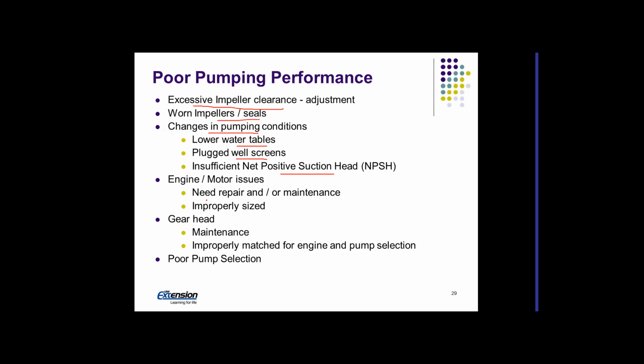So with motors and engines, sometimes it can be a repair or adjustment. Sometimes they're improperly sized. So it may have been put in for a high pressure system, but now we're running at low pressure, and it just doesn't meet the requirement anymore. Or we may have put in a different type of irrigation system. So sometimes they don't meet the needs, and they need to be changed, or at least we need to know that they're not running efficiently, so that when the opportunity arises, we can take that into consideration if we're doing a major maintenance requirement. The other thing is to look at the gear head. They require lubrication, and sometimes they're mismatched for the engine or pump selection. So that's something to consider. And then there's the pump selection itself.